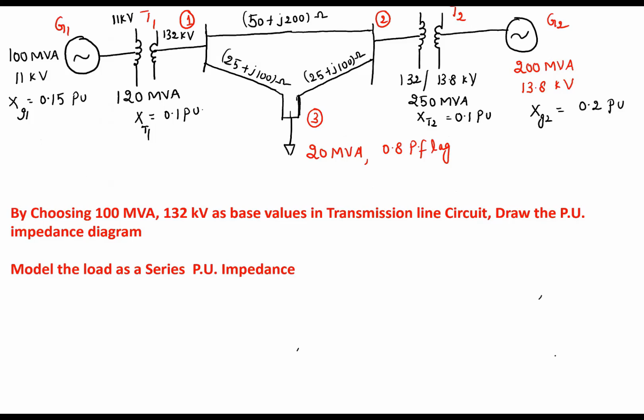Now if you see, this is one question. This is a classic question. If you understand this question, you can do any problem in the power system per unit network. So here he has given a single line diagram. And he's asking, by choosing 100 MVA as base MVA and 132 kV as base voltage, where in the transmission line circuit 100 MVA is the common base MVA for the entire power system network, and 132 kV is the base voltage in the transmission line circuit. Draw the per unit impedance diagram.